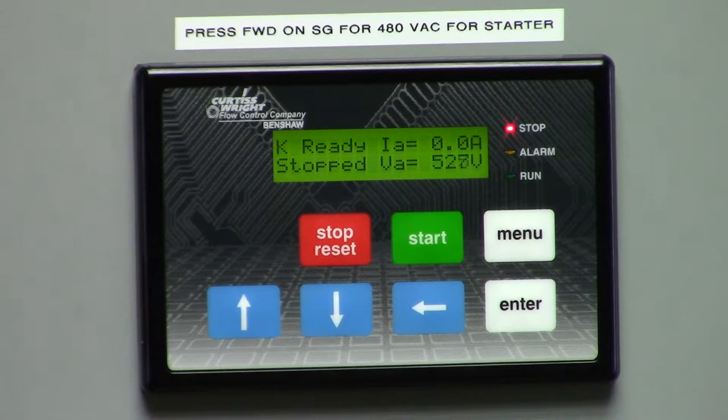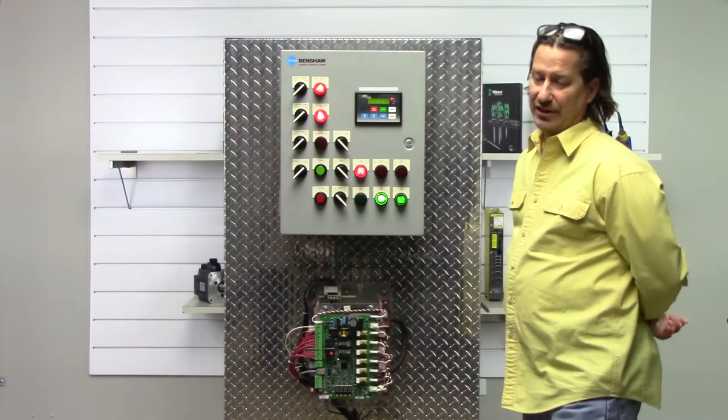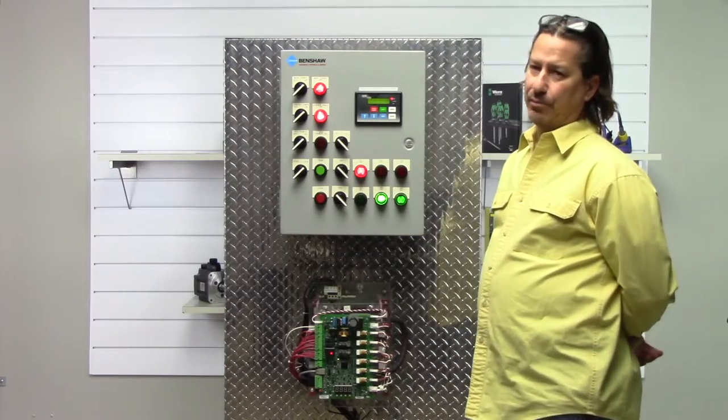As you can see right now, it says that it's in a ready mode, it's stopped, and it's also showing amps average on the top right-hand corner and voltage average on the lower right-hand corner. The voltage is the actual voltage that's feeding the starter, not what it's putting out.